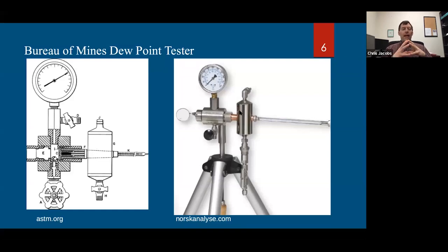So you may be wondering, how does liquid carbon dioxide work as a refrigerant? When liquid carbon dioxide is released from our storage tank, the expansion of the liquid and the high-speed evaporation causes a significant temperature drop inside this thermometer well here. So the temperature could drop very quickly. Now, liquid CO2 can actually be used to determine dew points as low as 0 degrees Fahrenheit, minus 17 Celsius. So unless we're talking about gases really, really cold, we can use liquid carbon dioxide.